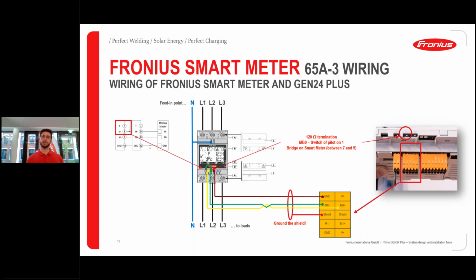And the fourth and last one is to have 120 ohm resistors at the end of our Modbus line. On our Modbus RTU line, we always have a serial connection, not a parallel one. And of course, we have two ends on our line here. On those end components, we always need to make sure to terminate it. On the Fronius smart meter, there is a 120 ohm resistor already integrated, and we just put a short cable bridge from position 7 to 9 in this case, and we terminate this component, so this Modbus line on this end.